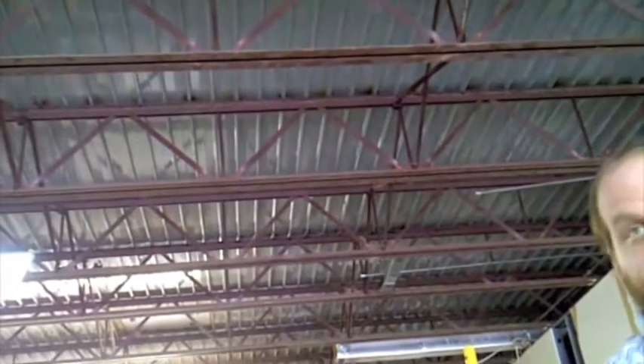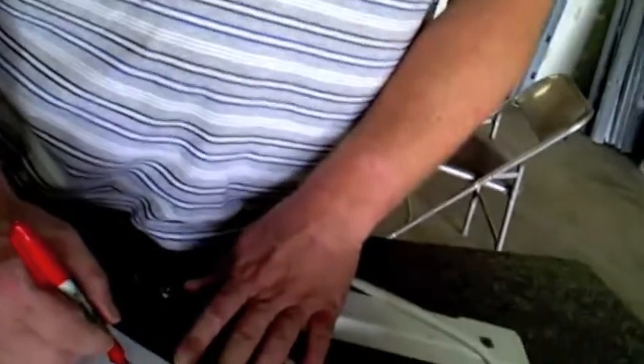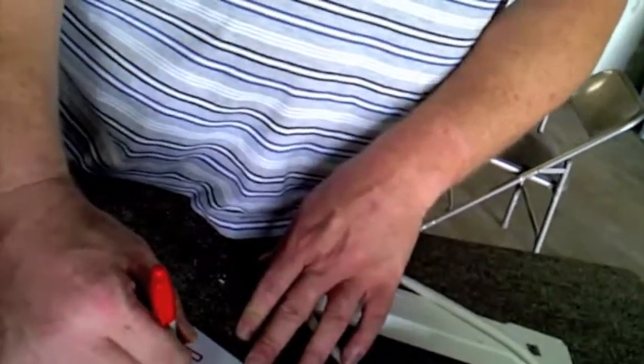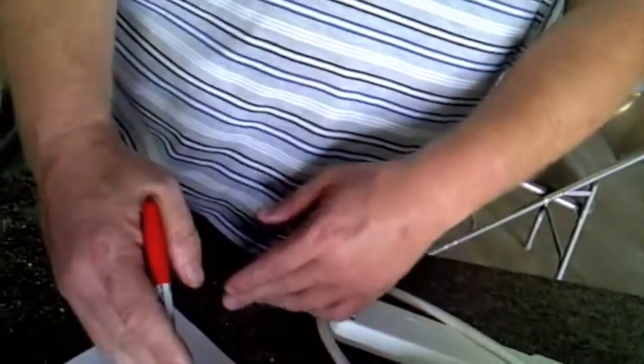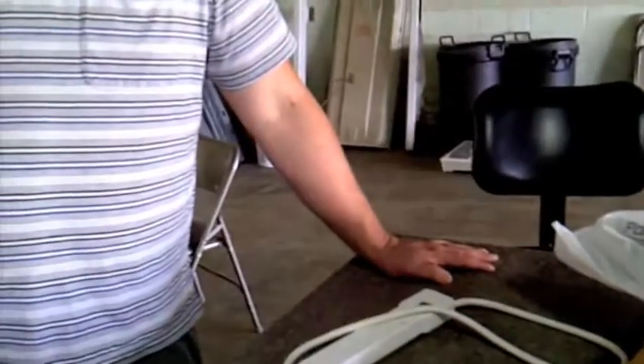I can also rig up a board-and-plug setup where when you're done, all you've got is plugs on the wall and you just attach your dimmers to it. Basically, wherever we decide to put the dimmers, we have a box on the wall with a receptacle instead of a dimmer switch. Then you have an attachment plug going to your box, and then your dimmers mounted in a prefabricated box. What that does is if it ever gets pulled, it's going to unplug rather than damaging anything. That seems like a really clean idea.